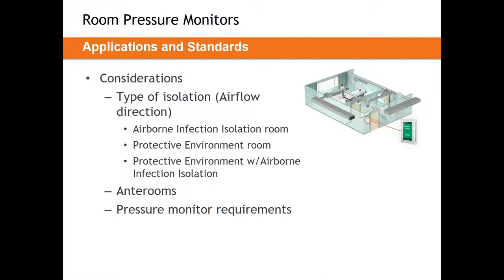The first and foremost consideration is what type of isolation it is. Is it airborne infectious isolation (AII)? Is it protective environment (PE)? Or is it the combination of the two — protective environment with airborne infectious isolation? Some of these will require anterooms and each has different requirements for room pressurization.